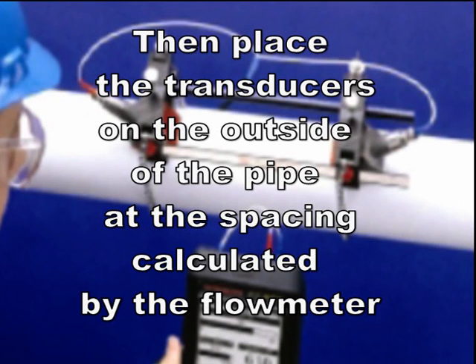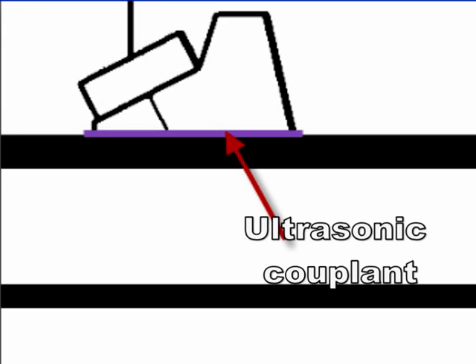We then place the transducers on the outside of the pipe, the spacing calculated by the flow meter. We also need to place an ultrasonic couplant between the transducers and the pipe, because an air gap will stop the ultrasonic signal.